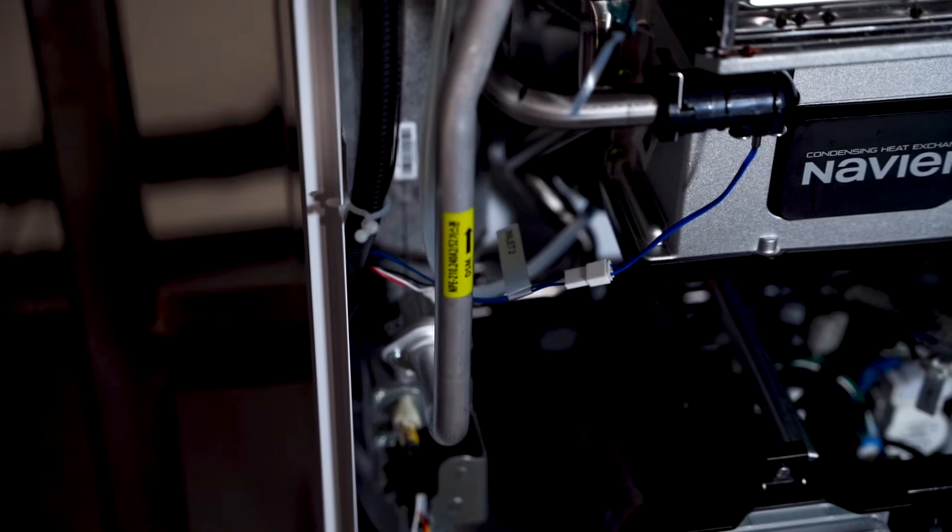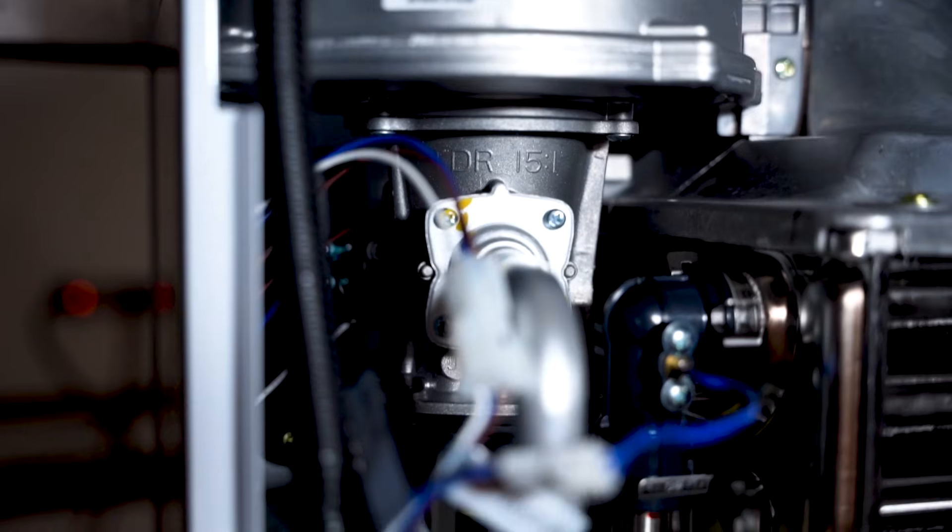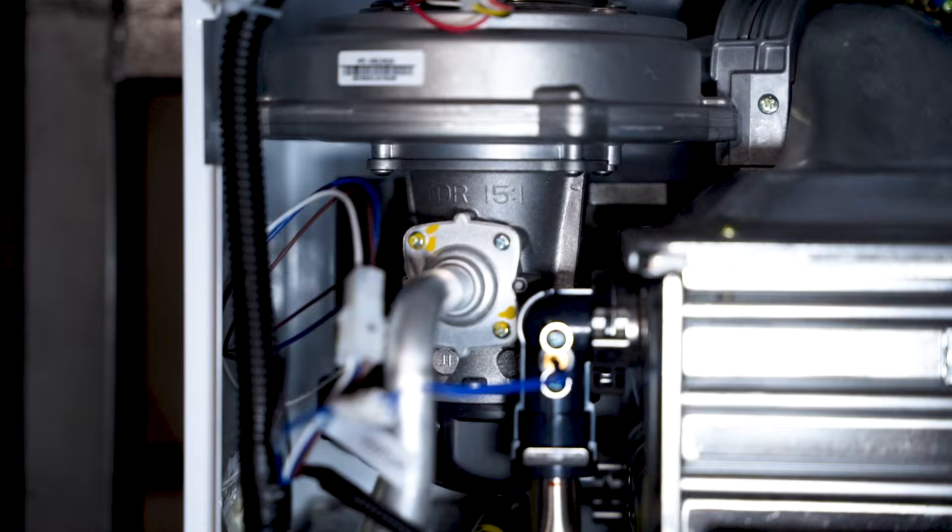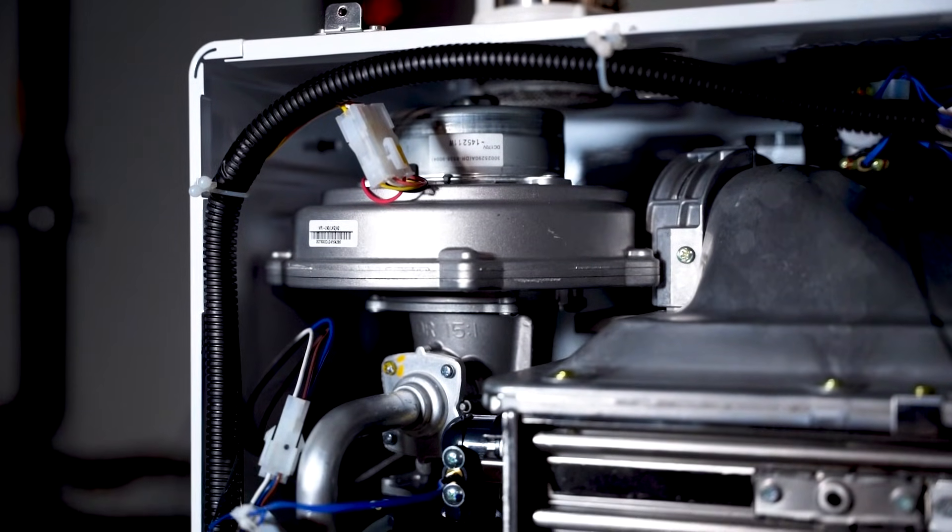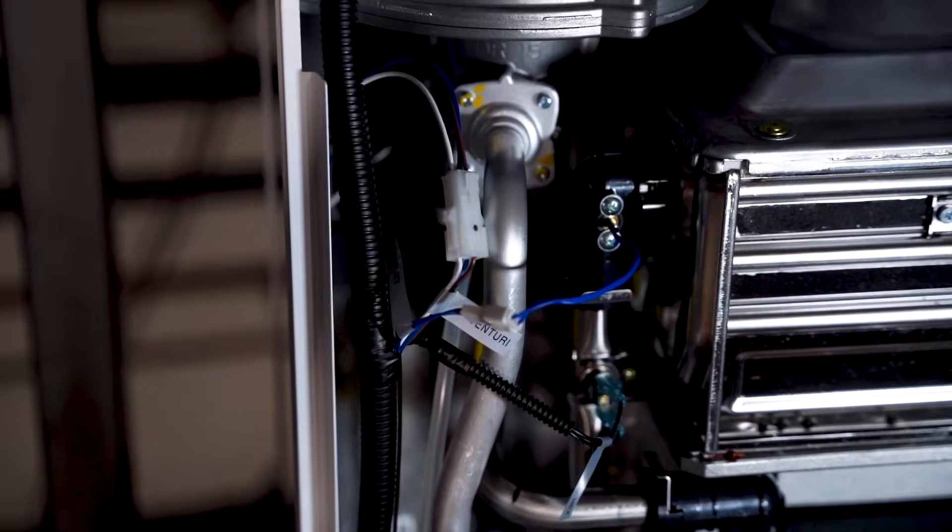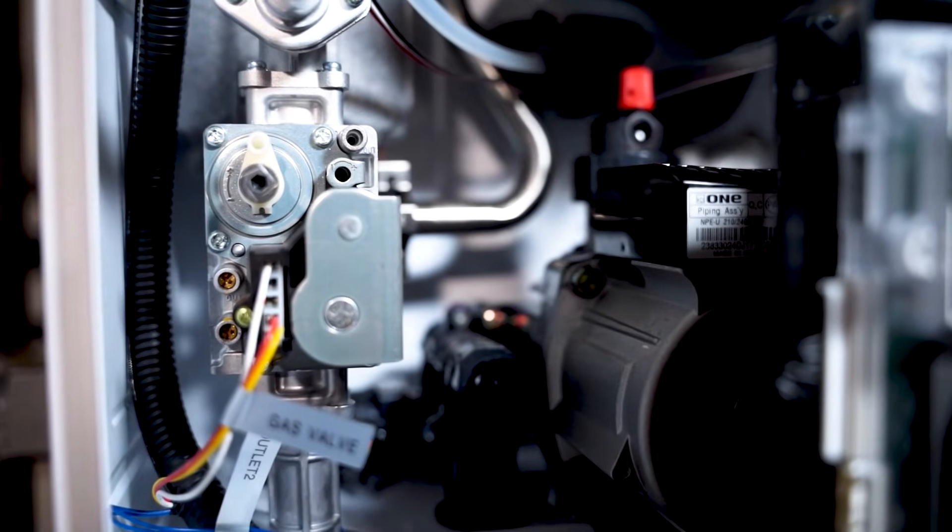The gas train is made up of three different components: the gas valve, the dual venturi, and the exhaust blower. Those three components work together to maintain proper combustion, and the gas valve also has redundant solenoid valves to provide an extra level of safety inside the unit.